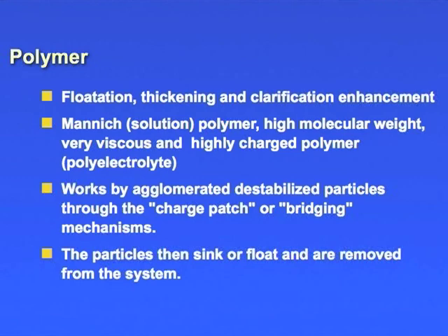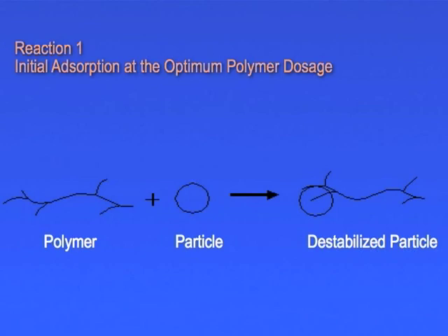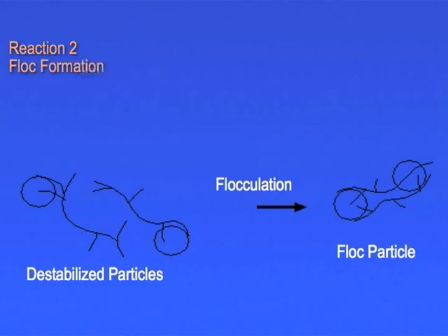It's an Mannich solution polymer, high molecular weight, very viscous, highly charged polymer, also called polyelectrolyte. It works by agglomerating destabilized particles through charge patch or bridging mechanisms. I'll show you that. Particles sink or float and are removed from the system. So here you have initial adsorption at the optimum polymer dosage. So you've got just enough polymer to take care of the particle there, destabilize it. And then you're going to start getting some floc formation. These destabilized particles will now join together and you start getting floc particles starting to join up.